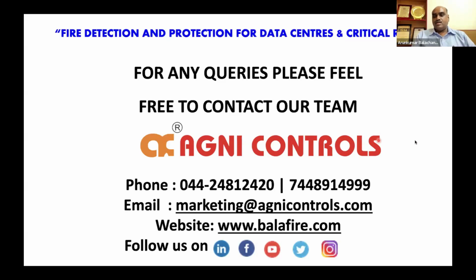Correct, sir. And also our IH226 detector is an EN 54-10 approved detector. It has LPCB approval and CE marking. And as you rightly said, prior to 2005, India was importing 100% of its flame detectors. And today, with a proud moment, we can say that we are now exporting flame detectors to four countries in Europe alone.